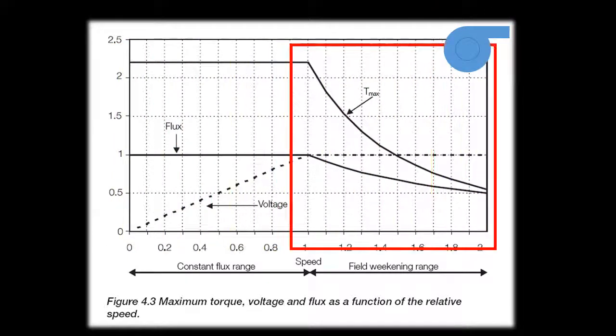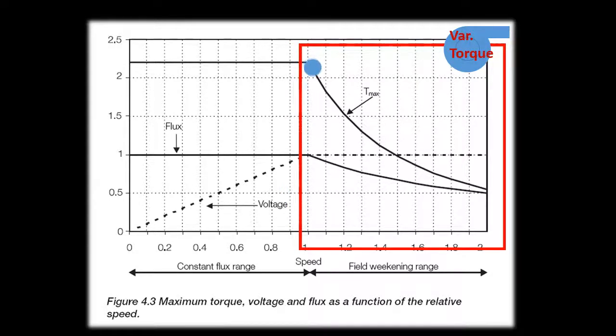If the motor speed enters the flux weakening range, full voltage is fed to the motor, and torque will drop off with increasing frequency. Using a motor in this region can be seen as a method of supplying a process with variable torque control via VSD.